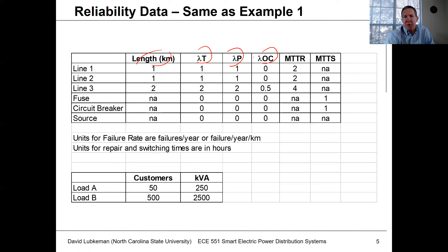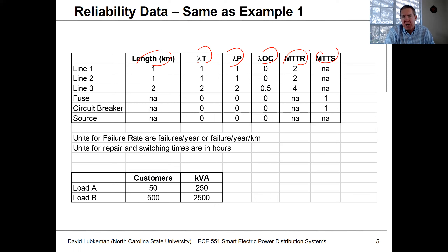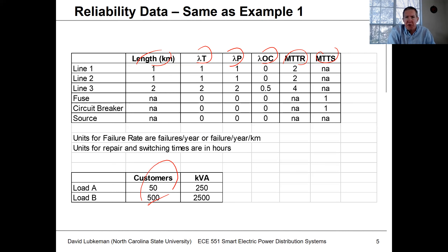We have a probability of an open circuit failure — this doesn't cause a fault but results in an outage — and then a mean time to repair the fault and a mean time to switch for a crew to operate the upstream switch. We'll have this statistical information for all elements in the circuit, focusing on elements most likely to fail like overhead line or cable failures. We also need customer counts because our indices are weighted by the number of customers at various locations.